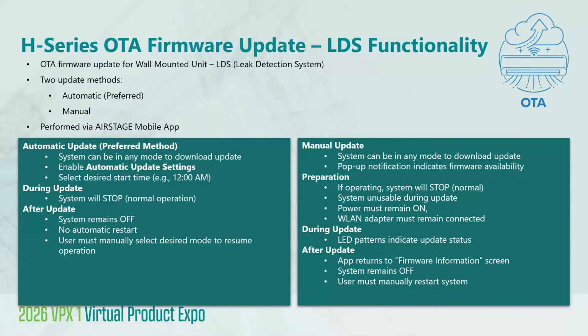The software update can be done via two methods. One is automatic, the other one is manual. Under the automatic method, once the Wi-Fi is commissioned to the indoor unit, you go to the AIRSTAGE mobile app and the automatic update settings page. And on the page, you have the option to select the time that you want the update to happen. Once you do that, and on the desired time, the unit will start updating the software automatically. And when this happens, the unit will stop operating. The unit will remain on, but it will stop operating. And once the update is complete, the system remains off. All you have to do is manually turn the system on and set it to the desired mode to continue operation.